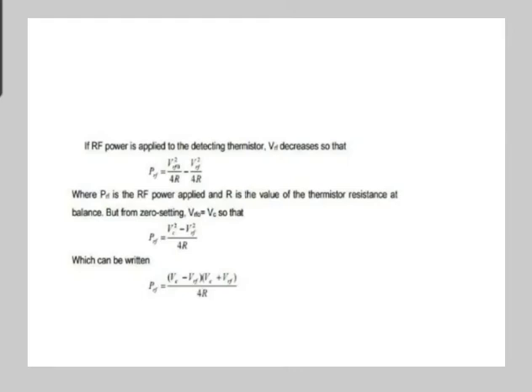Power meters are also based on self-balancing bridges, which operate on the principle of power substitution. Initially, these circuits apply some DC and some audio frequency power to the bolometer in order to balance the bridge. And the bridge is unbalanced when the microwave power is incident on the bolometer. This unbalance is sensed by an electronic circuit, and the circuit is designed in such a way that the balance is restored by removing an equivalent amount of audio frequency power from the bolometer. So a VTVM is used to measure this reduction in audio frequency power, and it also shows the microwave power under measurement.